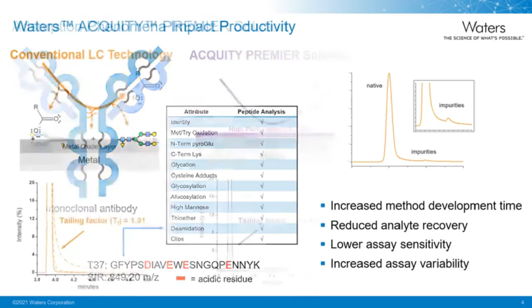As shown in the chromatograms on the bottom of the slide, using the same 3 synthetic peptides from before, the same analysis was carried out on a conventional LC system and on an Acquity Premier system. As noted in the slide, the peptide with 4 aspartic acid substitutions produces a broad peak with a tailing factor of 1.91 on the conventional system, but on our Acquity Premier system, the 3 peptides overlay with each other almost perfectly, with the tailing factor of the most acidic peptide reduced by 42% to a value of 1.10, demonstrating how effectively Acquity Premier technology can minimize analyte surface interaction for increased chromatographic performance.